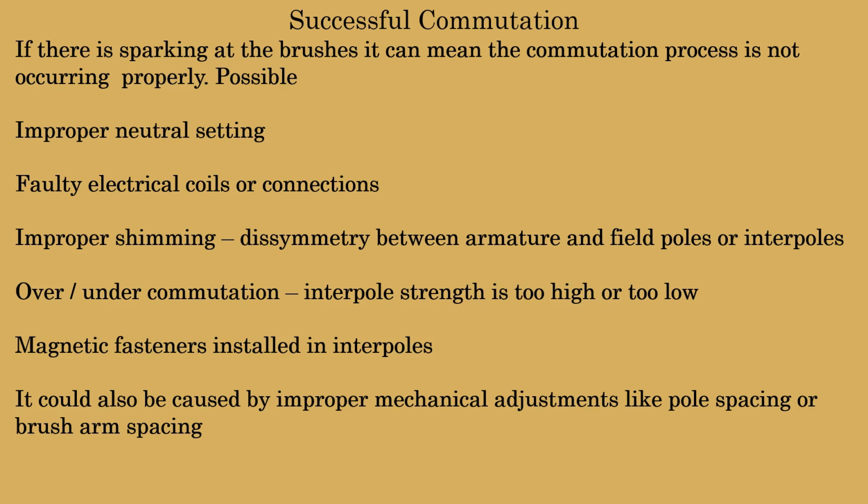If there is sparking at the brushes, it can mean the commutation process is not occurring properly. It's possible, not always what might be happening, but it is possible.